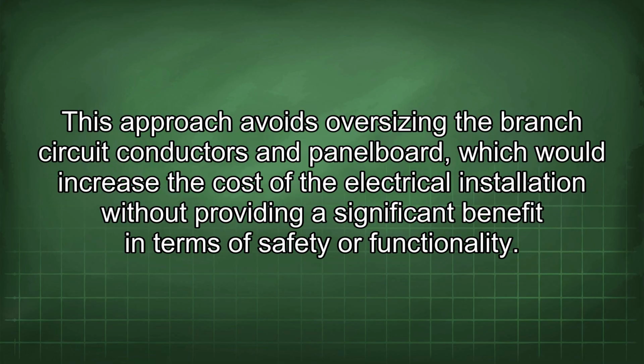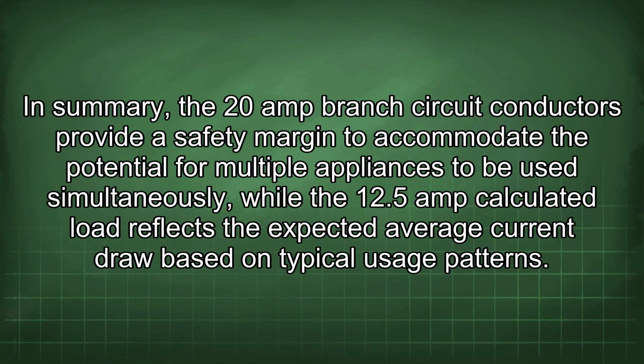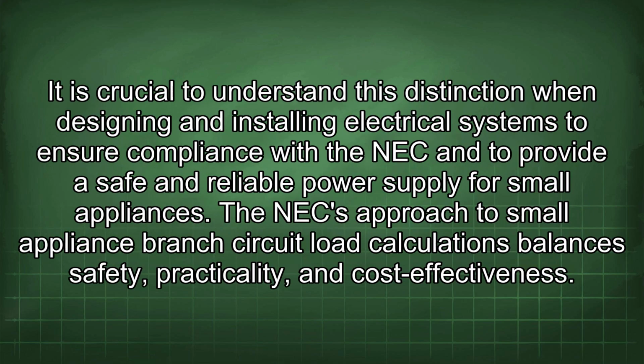This approach avoids oversizing the branch circuit conductors and panel board, which would increase the cost of the electrical installation without providing a significant benefit in terms of safety or functionality. In summary, the 20 amp branch circuit conductors provide a safety margin to accommodate the potential for multiple appliances to be used simultaneously, while the 12.5 amp calculated load reflects the expected average current draw based on typical usage patterns. It is crucial to understand this distinction when designing and installing electrical systems to ensure compliance with the NEC and to provide a safe and reliable power supply for small appliances.